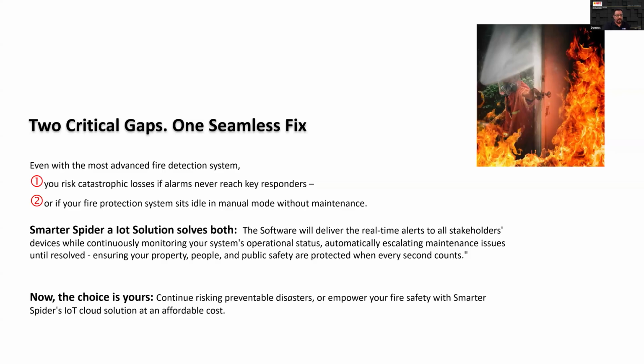You have two options: whether you risk the catastrophic losses if the alarm is never checked. Many times, if you look at the Jaipur incident, the report says the fire detection system never worked, and some are claiming that the sprinkler did not work. Now, the legal system is such that the entire management will be held responsible for not maintaining the fire system. If you look at most of the cases, whether an MRI hospital, the entire management is behind bars. It is a non-bailable offense if you're not maintaining the fire system as per the NBC. So there are systems which you can monitor 24/7.